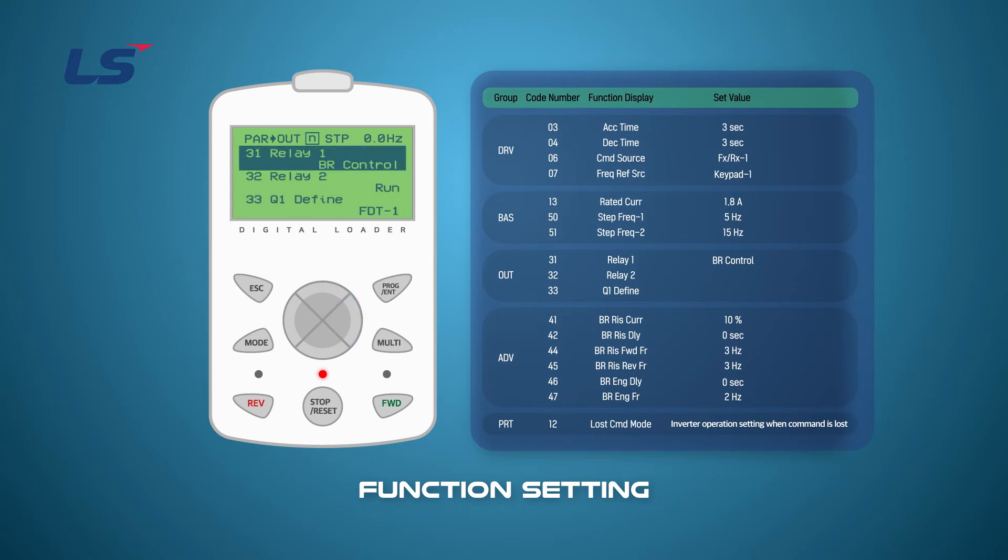Finally, when the run command or frequency command is lost, the operation is set to free run. When a lost command is issued to prevent the lift from falling due to the loss of command, the inverter operates in free run and the brake is closed.